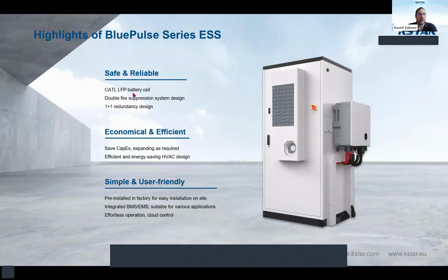So regarding the highlights of the product, inside there are lithium iron phosphate battery cells, which are produced by the CATL factory. And it has a 1+1 redundancy design, as I mentioned, for the double SOC values. It has a safe CAPEX. It can be expanded. It can be put together next to each other. And it takes less place to install. And the whole system is prefabricated in the factory. Only the inverter needs to be applied, and pre-manufactured cables need to be installed. It has also the cloud operation and the cloud control, and it can also be operated by the LCD screen on site.